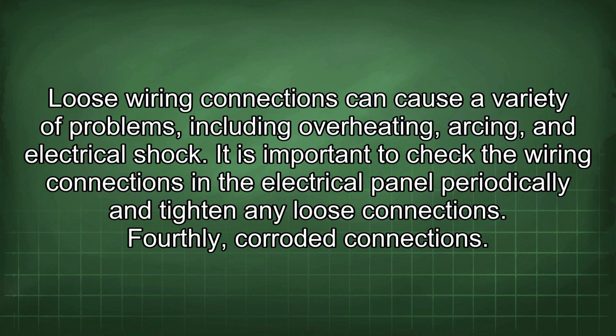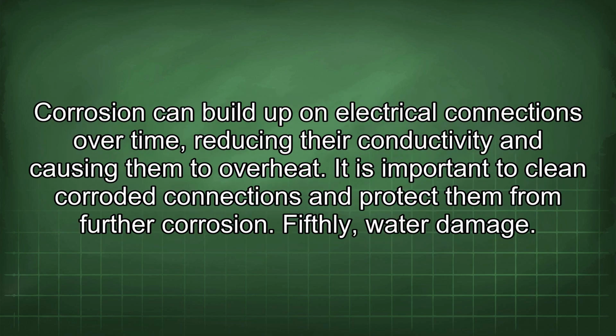It is important to check the wiring connections in the electrical panel periodically and tighten any loose connections. Fourthly, corroded connections. Corrosion can build up on electrical connections over time, reducing their conductivity and causing them to overheat. It is important to clean corroded connections and protect them from further corrosion.